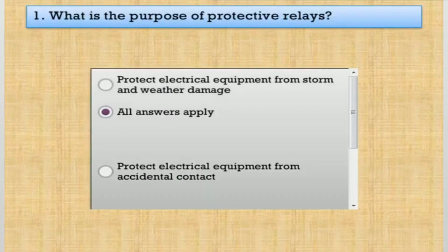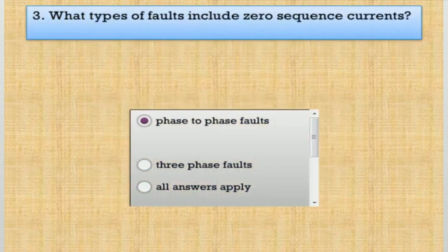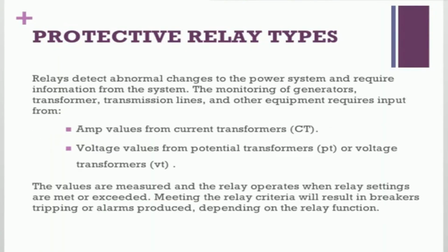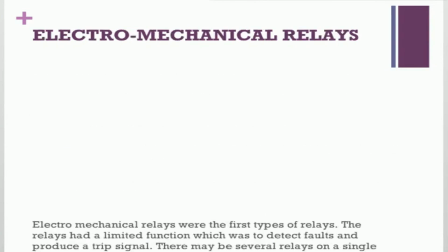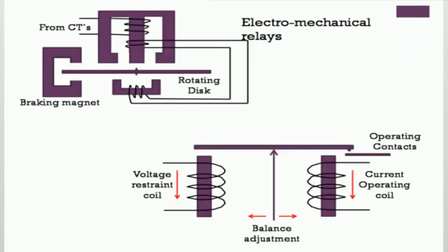Protective relays are devices that monitor the electrical network and initiate the tripping of circuit breakers when they detect anomalies. They are essential for mitigating damage during faults. Key types of protective relays include overcurrent relays, which detect and respond to excessive current flow. Differential relays compare the current entering and leaving a section of the system to detect faults. Distance relays measure the impedance of a line to detect faults based on their distance.